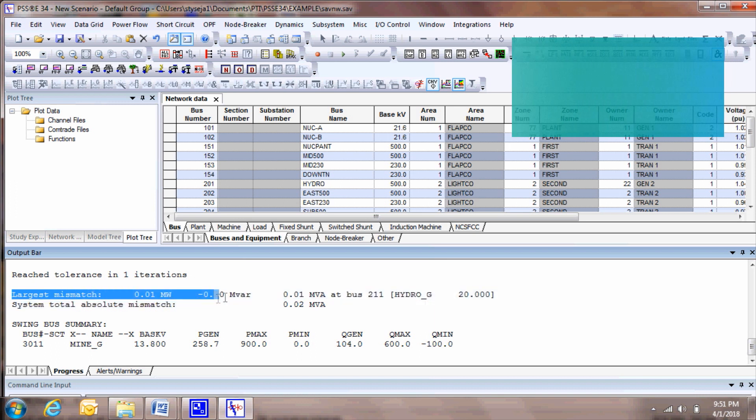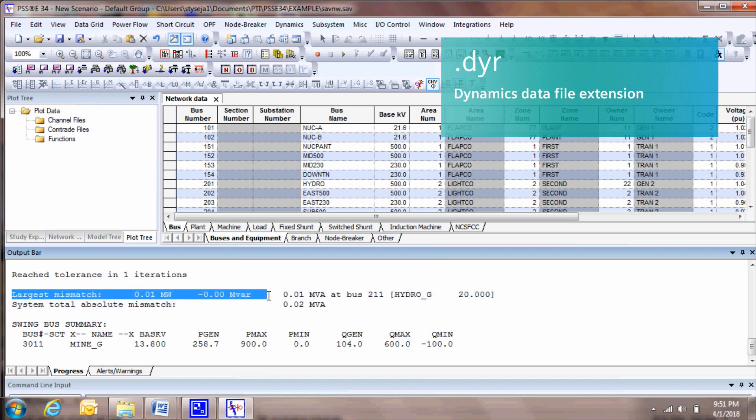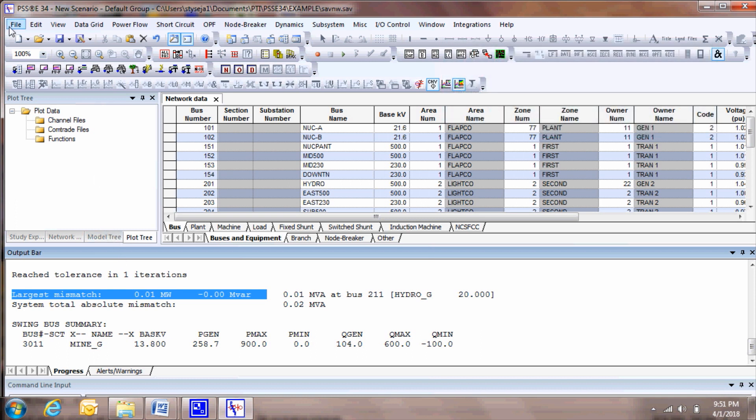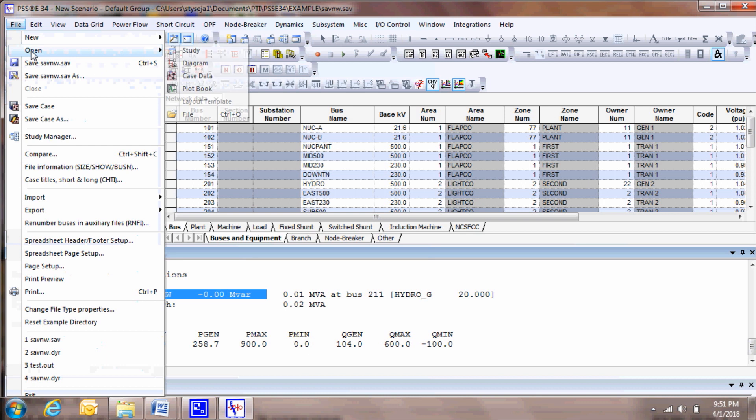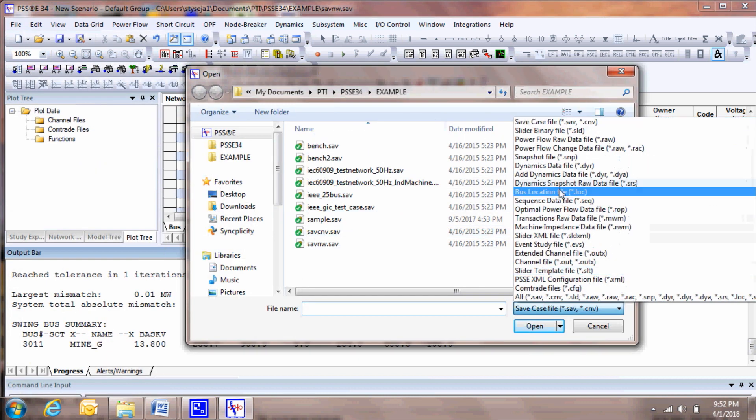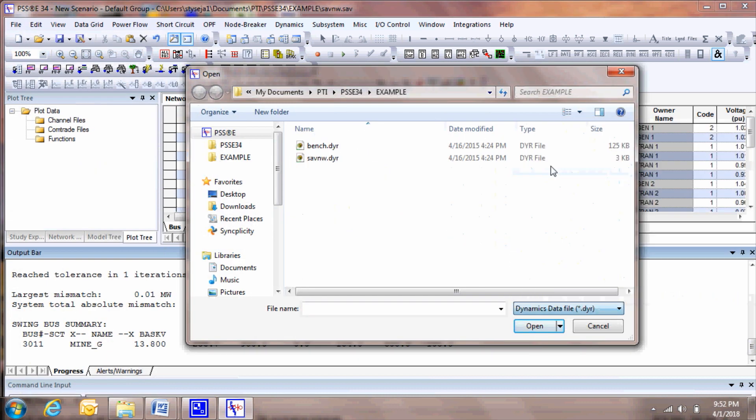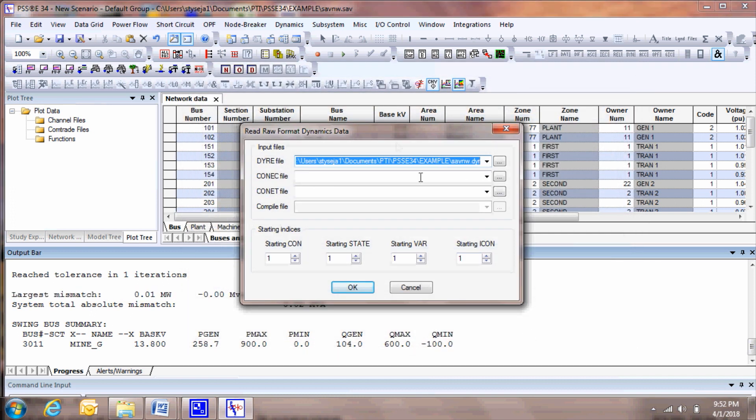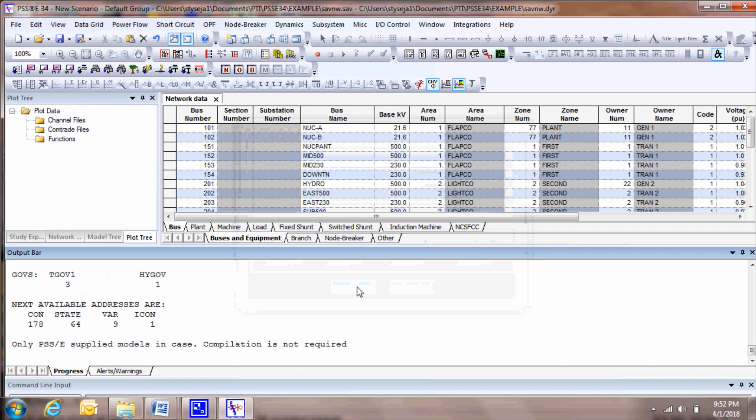The Dynamics data is contained in a file with the extension DYR. The example DYR file we will use for this illustration is the savnw.dyr. To read the dynamics data, go to File, Open, and select the file type Dynamics Data File, select the file savnw.dyr, and select Open. This opens a dialog where you will see the name of the DYR file you just selected. Click OK, and PSSE reads in the dynamics data.